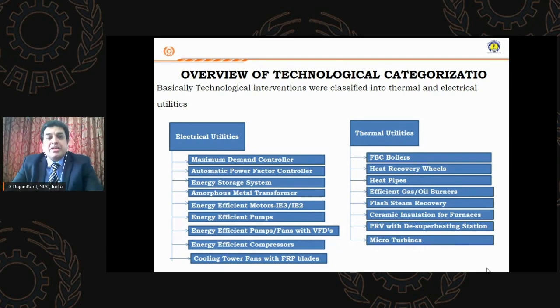All these technologies have been established by large scale industries, and they are all proven, with a payback period, the return on investment, that is very, very early. That saves not only your cost of fuel or electricity, but also improves the overall productivity of the plant. On the thermal side, you have FBC boilers, which we call fluidized bed combustion boilers. We have heat recovery wheels, heat pipes. I will go through how this will help SMEs in the coming slides. Then you have efficient gas and oil burners.